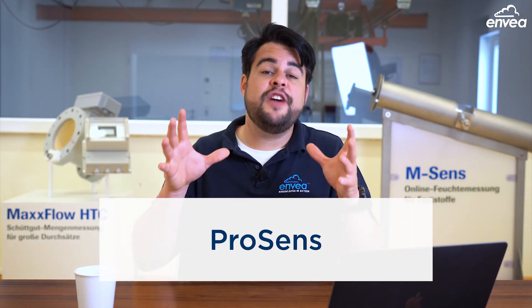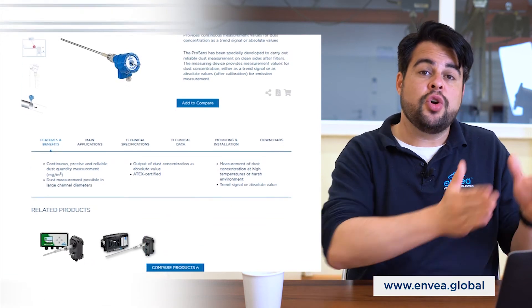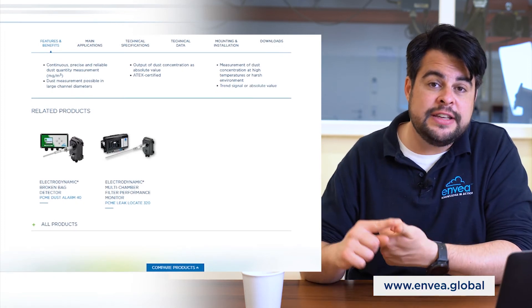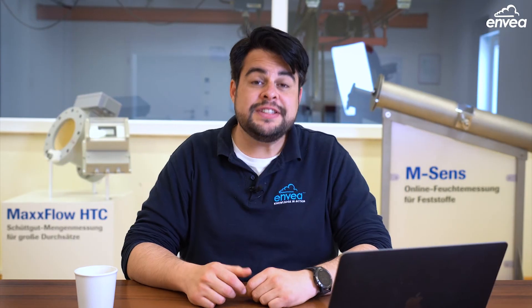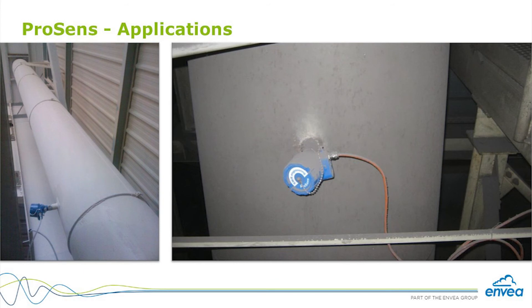But Dusty is just the first step into the emissions measuring range. When we want more than just an alarm — when we want measurement in mg per cubic meter — then we jump to the ProSens. The ProSens uses ENVEA's Electrodynamic technology, monitoring everything that happens inside the pipeline. The sensor goes on the chimney and has an external evaluation unit to deliver 4-20 mA, Modbus, and Profibus outputs. Using the isokinetic sampling or dosing method, the ProSens can be calibrated, giving an accurate measurement in mg per cubic meter.